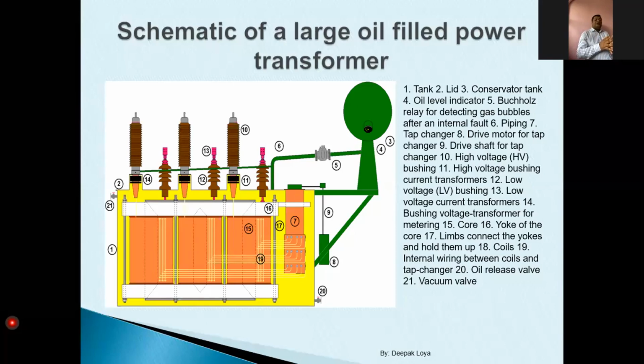Sometimes what happens is, when I have filled this transformer in the winter season, when my transformer was not on load, I have filled some extra quantity. And now it is the summer season and I am in Nagpur, the ambient temperature is around 47-48 degrees Celsius. Everybody has put on the AC, the transformer load is full. Now the oil is being heated to a higher level and the volume has increased. So oil will start spilling out. That should not happen. That's why I also have the oil indicator to monitor the higher level of this transformer.